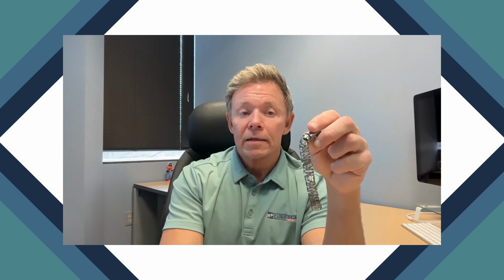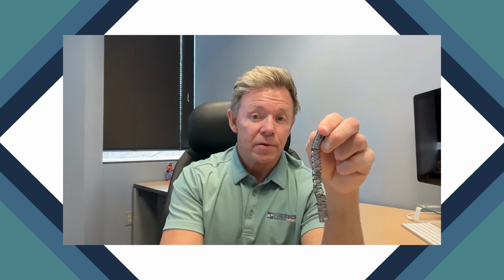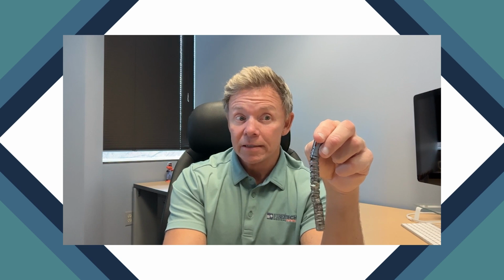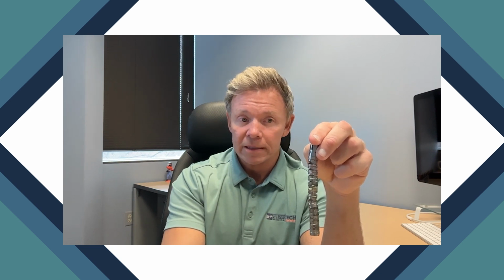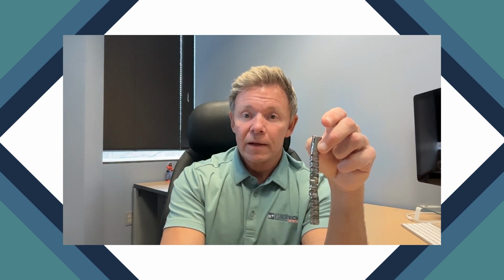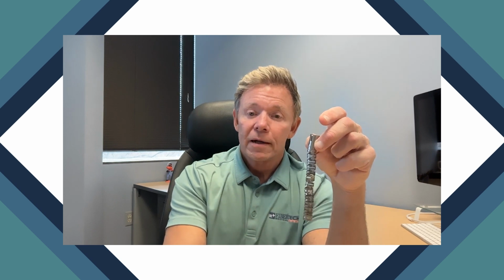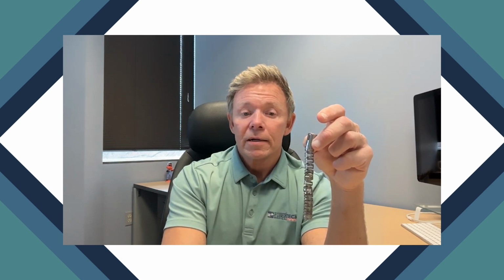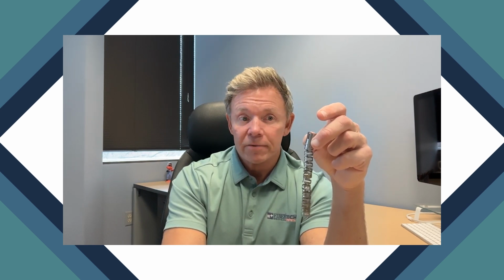Okay. And last, what happens is fluid gets in the scope. So probably, we might have talked about this in episode 1, but the worst enemy to the endoscope is getting fluid inside the scope. And that's why leak testing is so important. We always talk about leak testing, but if fluid gets into the scope, it actually will wash away the lubricant, okay? That protects this, makes it bend smoothly. And now you're really in a situation where it's going to feel tight. It might even feel grindy, if you will. And it's just not going to bend properly. So all of these varying factors come together and result in, well, pretty much the same end result. It's not bending properly, and this piece needs to be replaced.